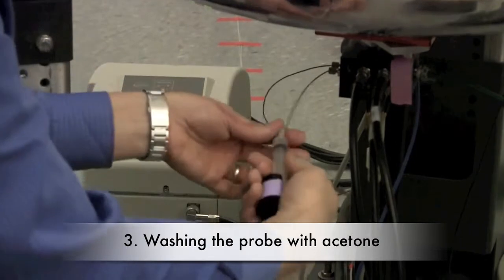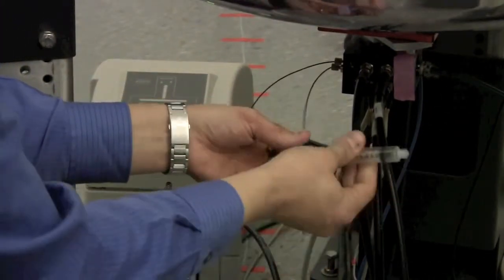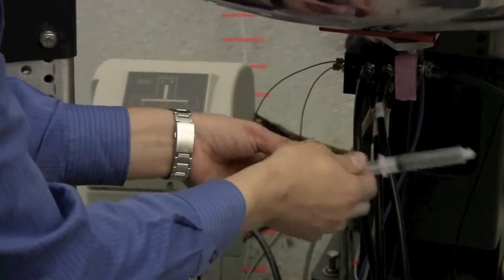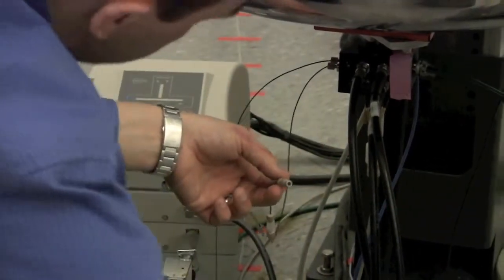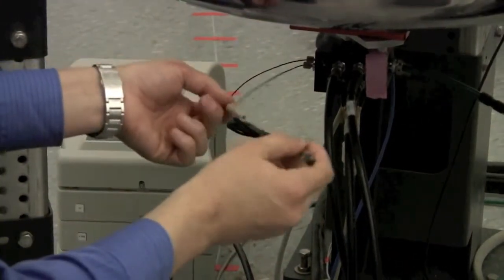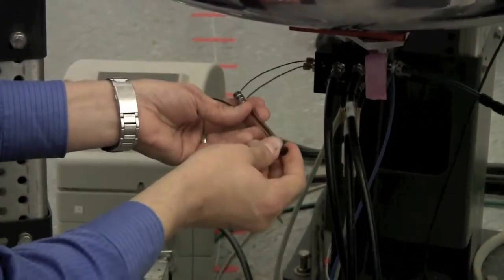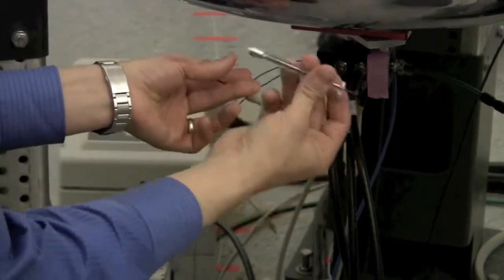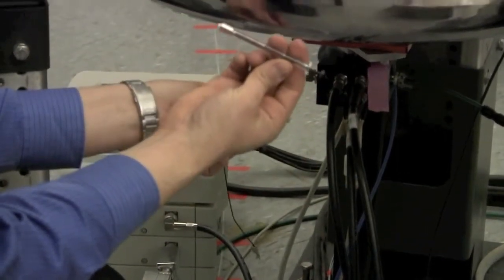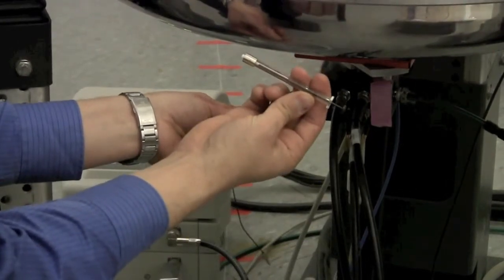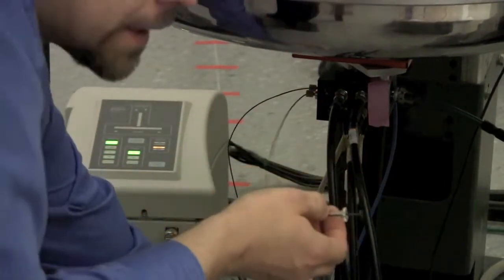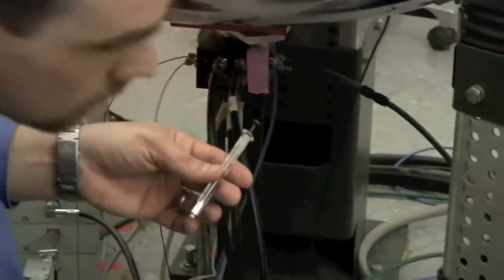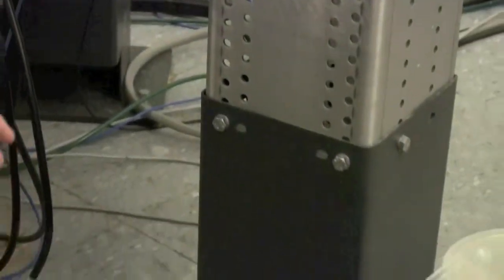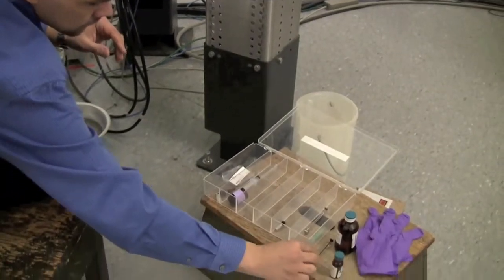And typically what we use to wash the probe out is acetone. Acetone is miscible with most solvents, and it dissolves a lot of different materials, so it's a good option to clean out and make sure that the probe is free of any contamination that might have built up in there from previous users. So we're going to use this 250 microliter syringe to flush out the probe with acetone. And we typically use deuterated acetone just because it's convenient and relatively clean compared to lab grade acetone.